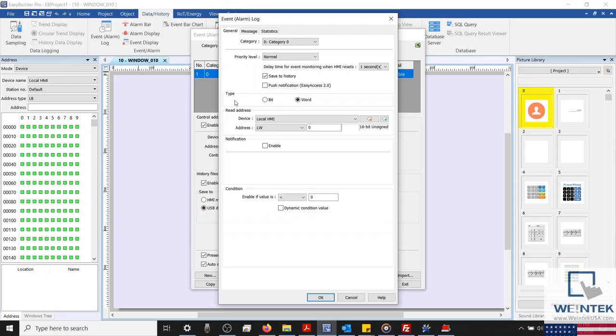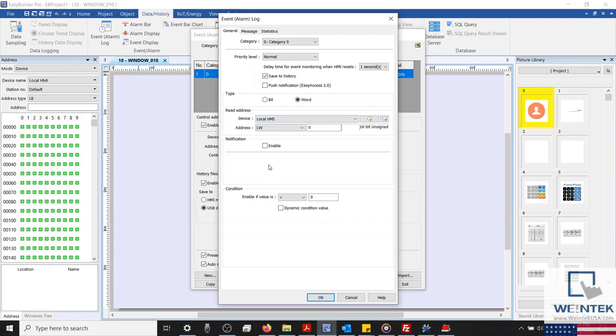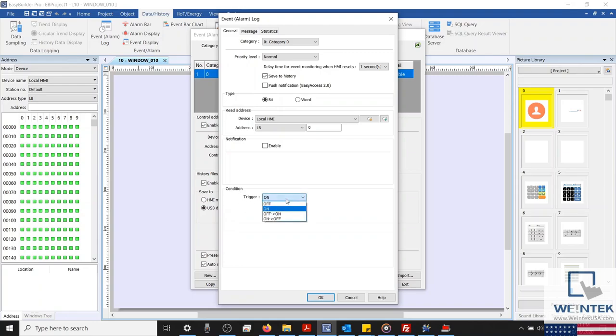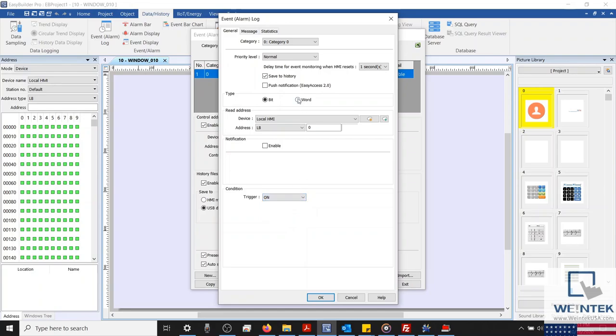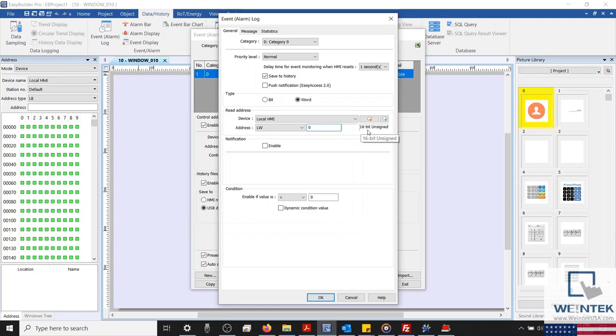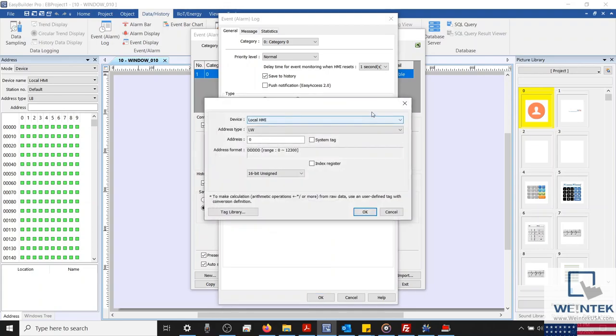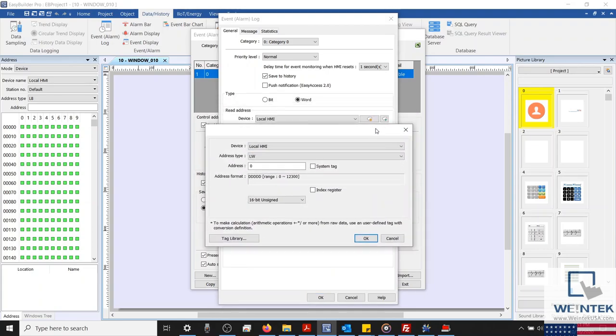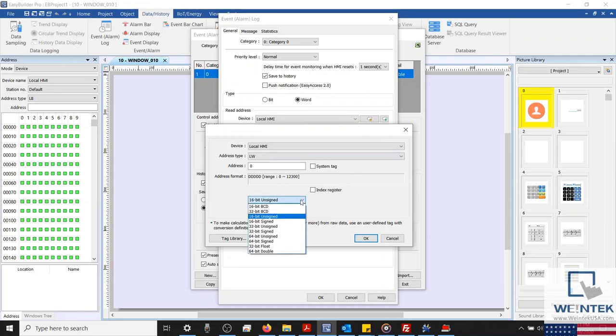Now, we'll need to specify if this event will be reading a word or bit value, as this will change the conditions available for selection. Just to get an idea of what conditions we can monitor, let's first select a bit value. Within our Conditions section, you'll notice that we can monitor four different conditions related to a particular bit state, which include either when the bit is in the on or off state, or during a specific state change. Although for this example, we're going to read a word value, and within our read address, you'll notice that our alarm is configured to read our internal register, LW0. Currently, we have our data type set to 16-bit unsigned. To change this, we'll select the Settings button on the right-hand side, and configure the data type within our dropdown list.